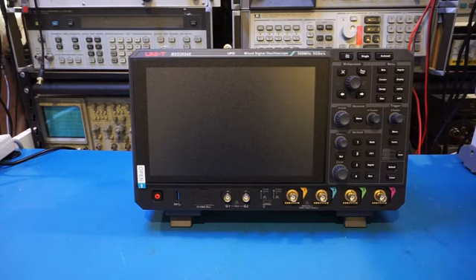Combing through the specs, I can see some other differences as well. For example, the maximum memory depth of the MSO3000X series has increased to 500 M points versus the 100 M points in the MSO2000X series. The segmented memory in the MSO3000X series can store up to 250,000 frames of real-time waveform data versus the 125,000 frames in the MSO2000X series. And the 3000X series also supports Wi-Fi connectivity, whereas the 2000X series only supports Ethernet.